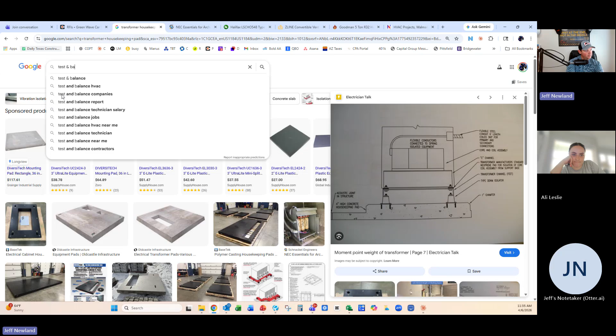Let me show you, because that actually kind of explains it. There we go. So what happens is the guys go around and put this cone with this meter on it up against the actual flow, either on diffusers, depending on whether it's a supply or a return. Then it calculates how much air it's actually putting through via the CFMs, and they'll check their plans and say, okay, this room is supposed to have whatever the number is.